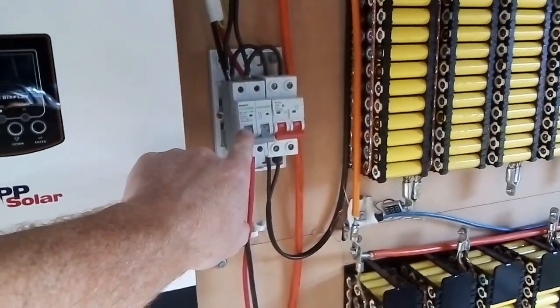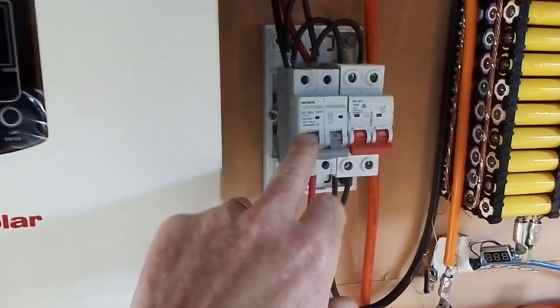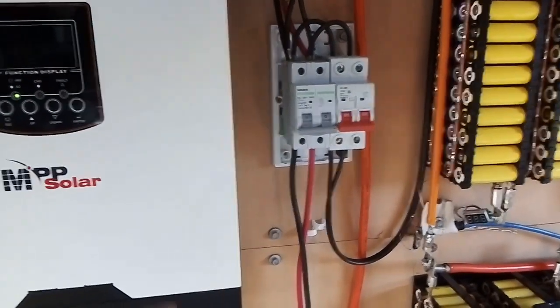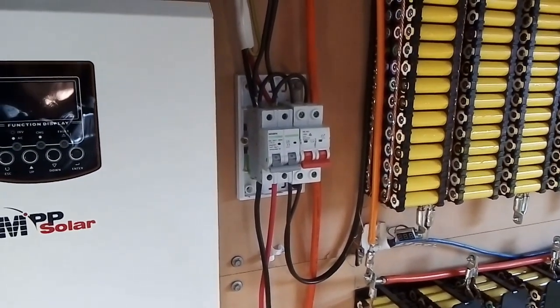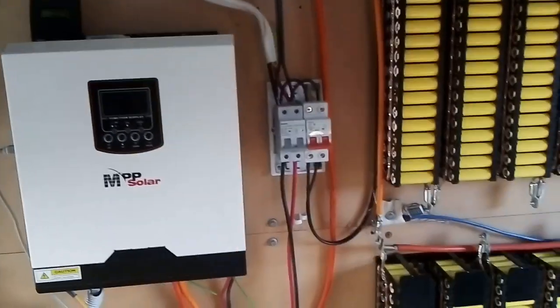This cost me 40 Australian dollars — another 40 down the drain. The first one I replaced was a 50 amp inline fuse, but this switch can do 50 amps, so it did stress out and need replacing. The device protection should be rated higher than the inverter — about 1.25 times. So if you have a 50 amp inverter, make it a 63 amp fuse. Anyway, please subscribe, hit the bell, drop comments, and point out what I'm doing wrong. All these solar wires need to be changed and made safer. Thank you very much, see you later.